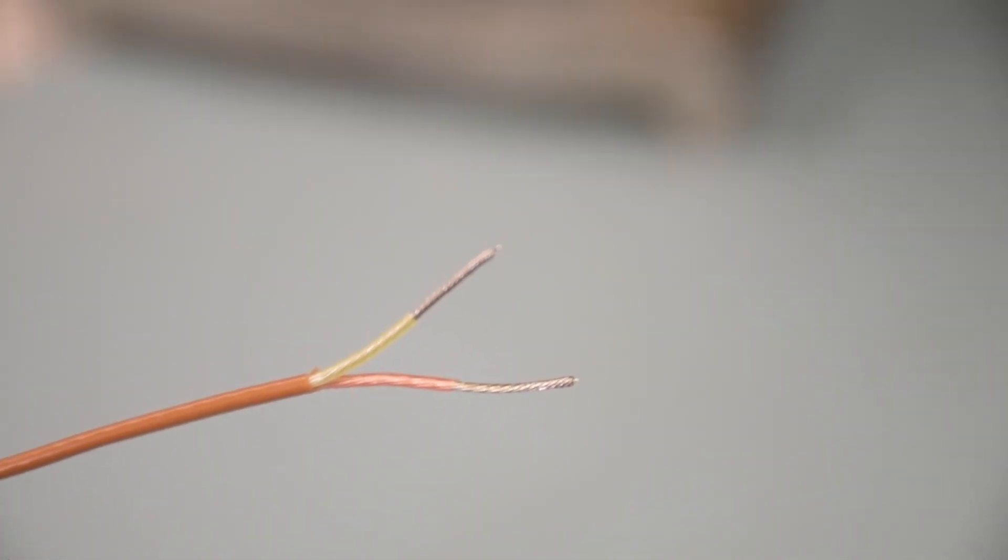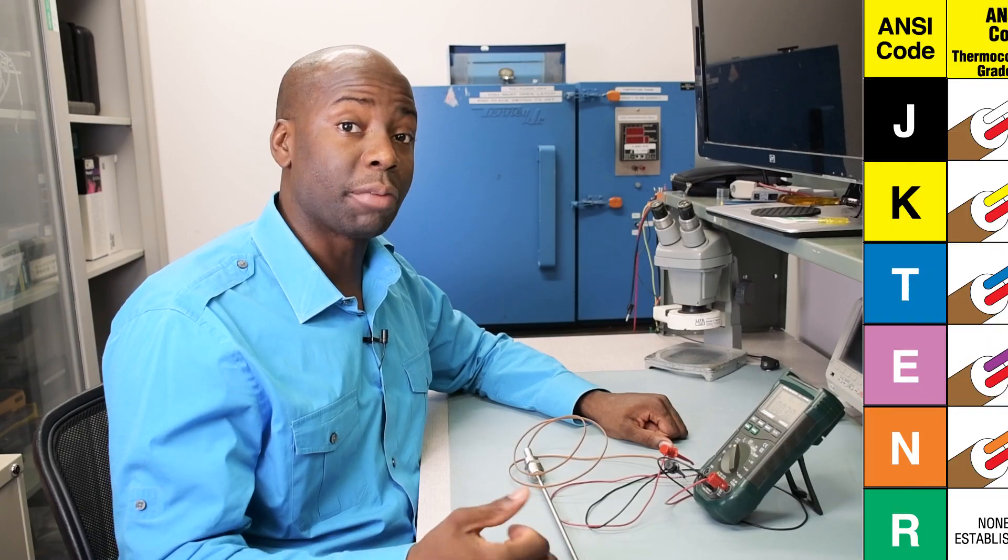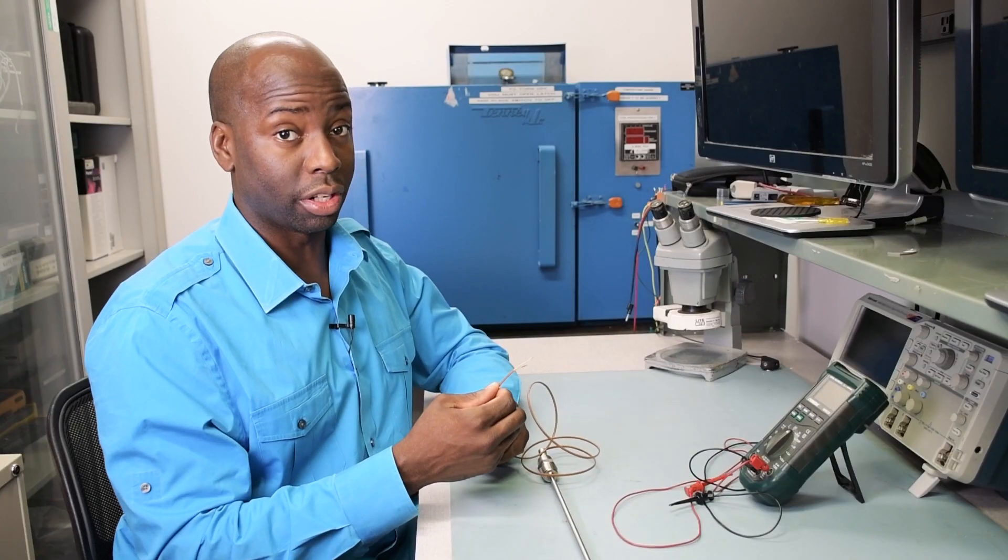One wire is colored with a red insulation and another wire is colored with a yellow insulation. If I check my thermocouple color code chart, a K-type thermocouple has a yellow and a red insulation. We might have a thermocouple here, but let's dig deeper.